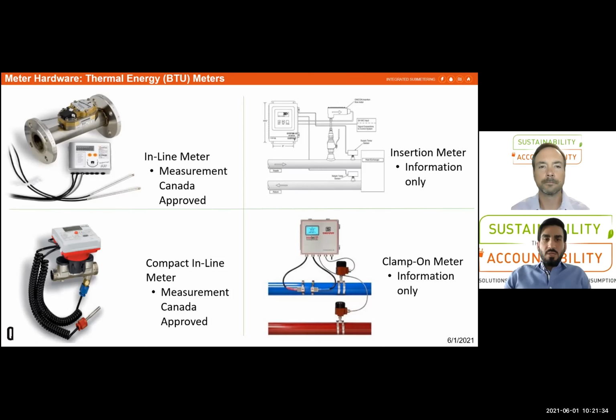So we categorize thermal meters in three main groups, broken into four categories. Inline thermal meters, which are the only type that can be used for revenue or cost sharing applications, typically offering a better measurement accuracy and lower maintenance requirements, specifically in the flow where the flow component is a non-mechanical type, meaning having no moving parts.